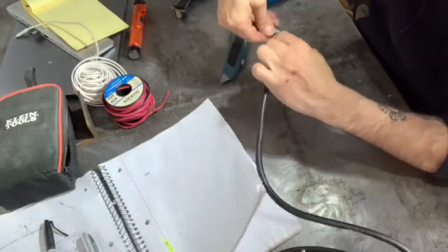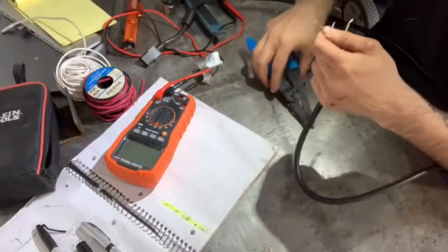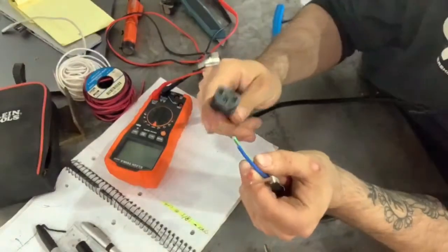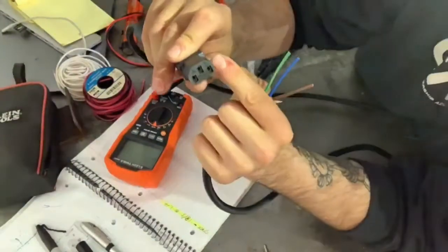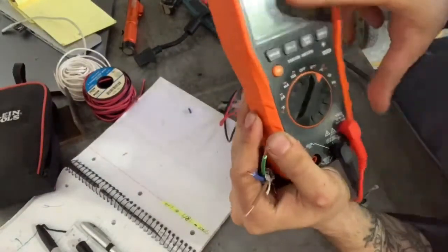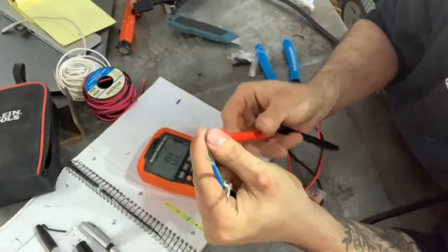It's shielded — I mean it's wrapped in a steel jacket. Now we're going to check for continuity between the end of the cable and the C14 connector to determine what is what. Remember: this is the hot pin, this is the ground pin, and this is the neutral pin. For continuity, we're just going to go ahead and turn our multimeter to the continuity setting and ensure that it's on the ohm setting. So we'll go to the green wire here.